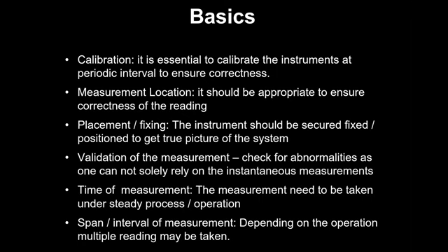Okay. Then comes the time of measurement. This becomes more critical for large plants, but otherwise also, when we are doing a measurement, we have to see that the process is at normal condition. If there are some deviations or variations in the process, correspondingly there are going to be process equipment variations. Say when you are doing a chill water capacity test, you're trying to find out the TR of the chill water, and if the plant doesn't have any chilling load, then definitely it is not going to show you correct readings. It is going to show that TR is less and kW per TR is high, which is not a normal case. That is why whenever we are doing measurements, we need to ask the people: is everything normal? Is there any abnormality in this system?